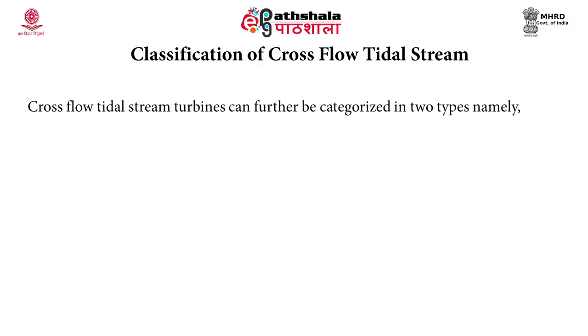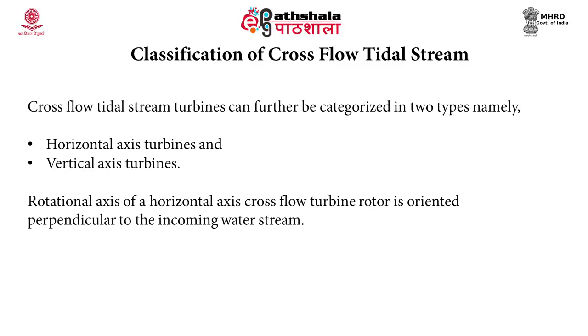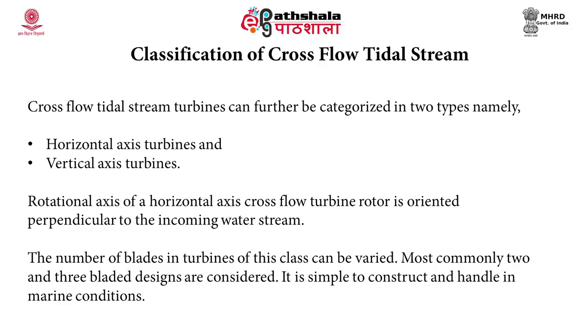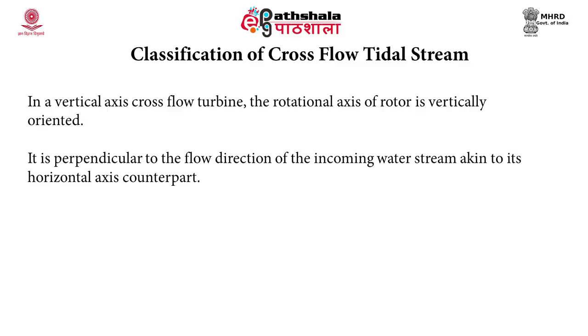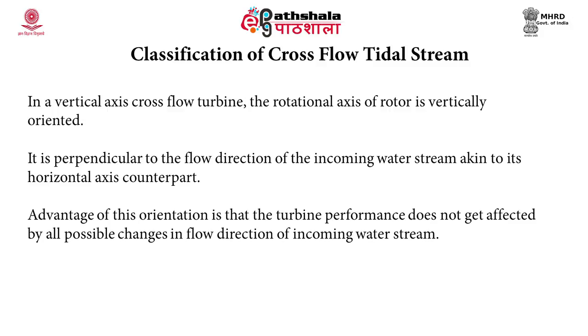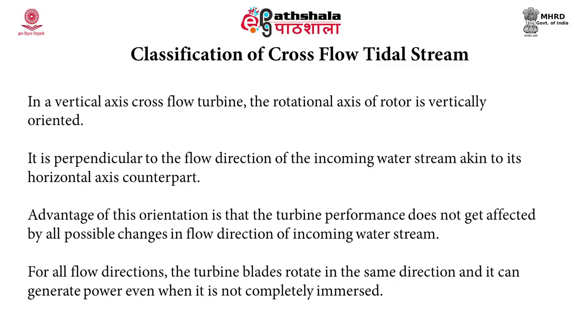Cross flow tidal stream turbines are further categorized into horizontal axis turbines and vertical axis turbines. The rotational axis of a horizontal axis cross flow turbine rotor is oriented perpendicular to the incoming water stream, and the number of blades can be varied, with two or three bladed designs being most common. In a vertical axis cross flow turbine the rotational axis of the rotor is vertically oriented and perpendicular to the flow direction. The advantage of this orientation is that turbine performance is not affected by changes in flow direction, the turbine blades rotate in the same direction for all flow directions, and it can generate power even when not completely immersed.